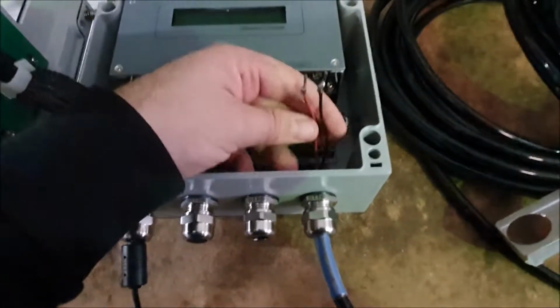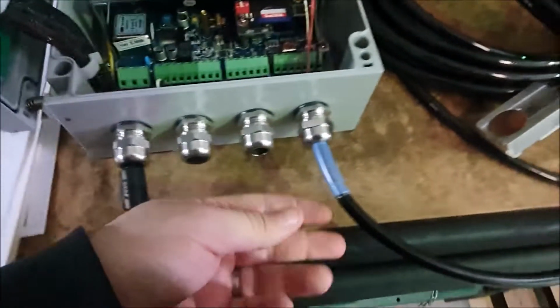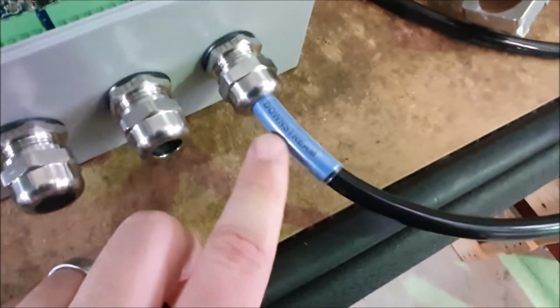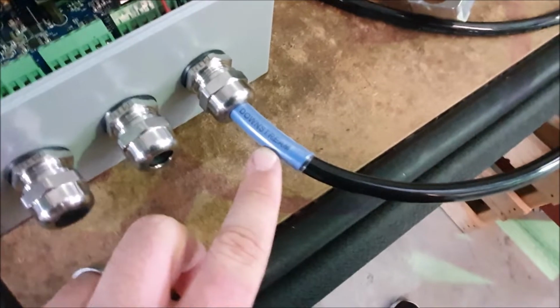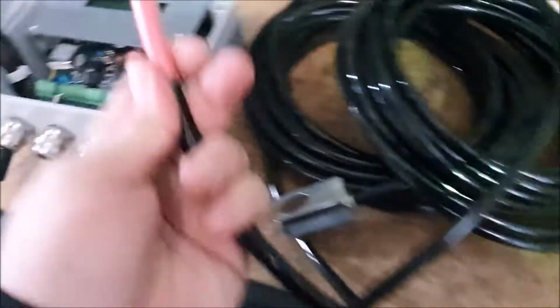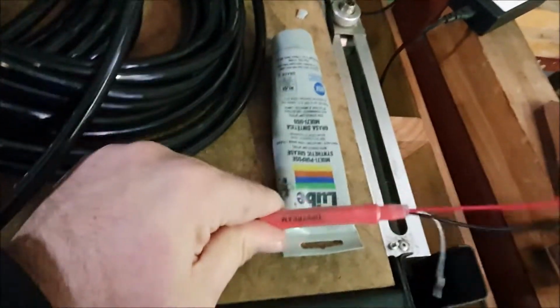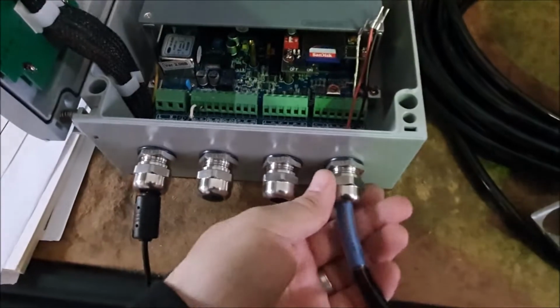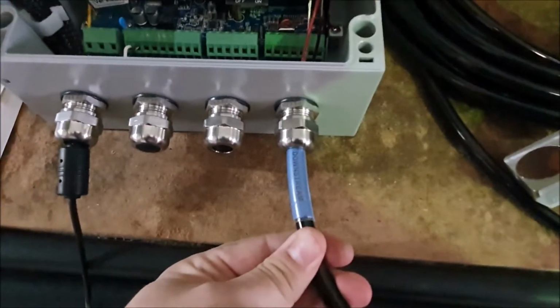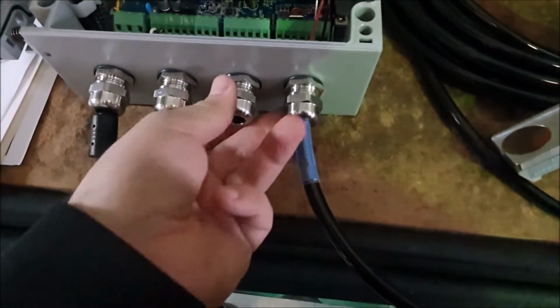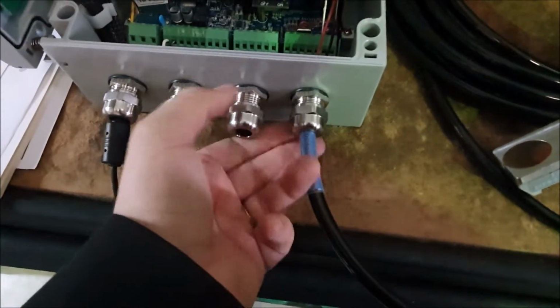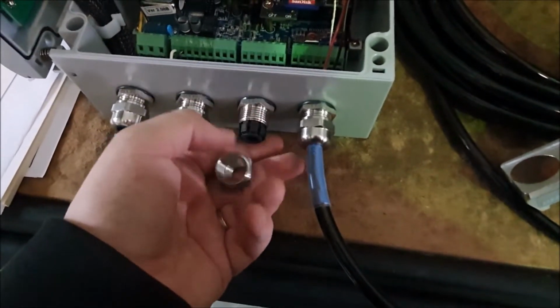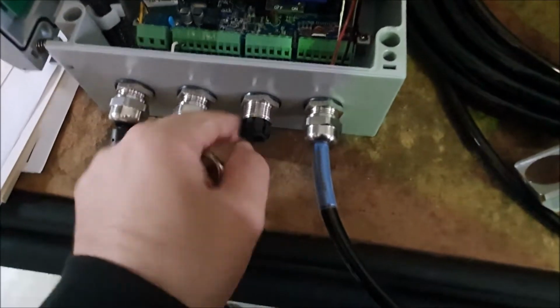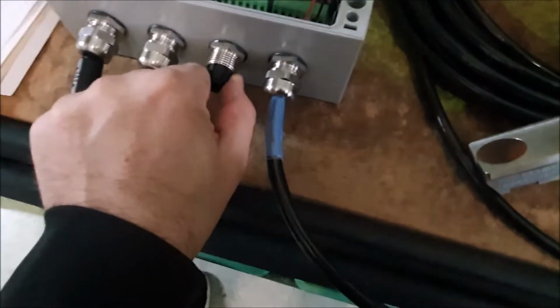And now we'll put in the transducers. So on your transducer cables you'll see it's got these markings, downstream, and then on the other one you'll have upstream. Okay, so that just shows the direction the transducers need to be mounted. So I've already got one of these cables running in through the cable gland. I'll just show you putting in the other one. So if you undo the cable gland and pull out this rubber washer as well.